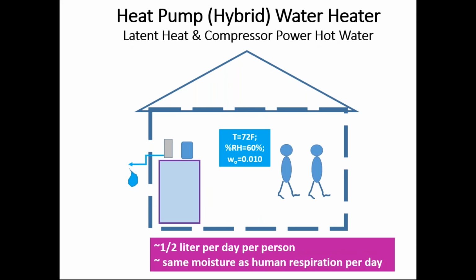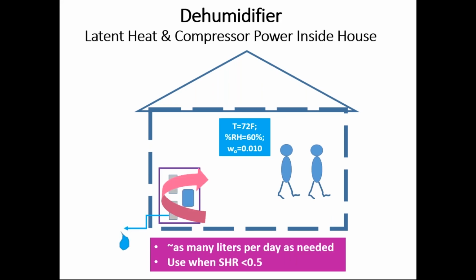Heat pump water heaters, from our research data, we roughly see about half a liter per day per person. And the interesting thing about that, from the previous table on human moisture generation in a home, is that our respiration roughly puts about half a liter of water in the air per day. So your heat pump water heater's operation scales with the number of occupants, and the moisture it's pulling out, from our data in any case, seems to scale with the number of people nicely. And it's a significant contribution.